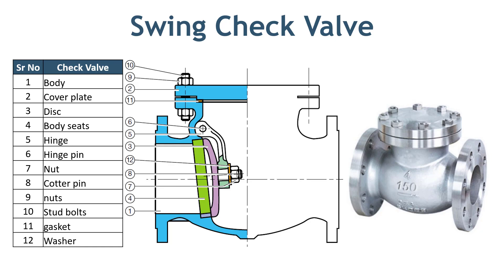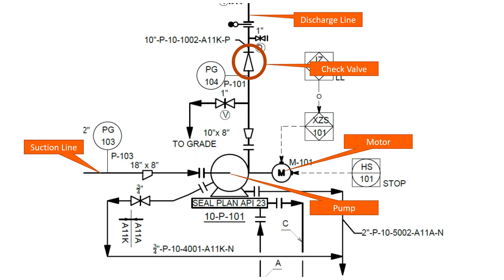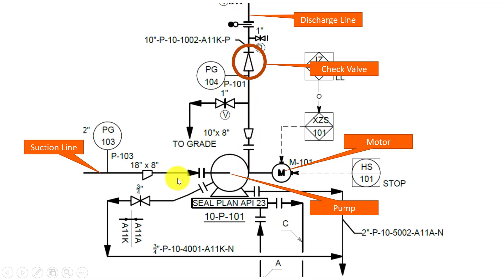Let's assume a simple pump or compressor system like the one shown in this P&ID. The pump inlet is connected to the storage tank. The pressure in the inlet pipe is less compared to the pump outlet. In case of sudden power failure, the pump will stop working and there will be a large differential pressure between the pump suction and discharge line. The moment forward pressure stops, fluid from the pump discharge line tries to move backward towards the lower pressure system.